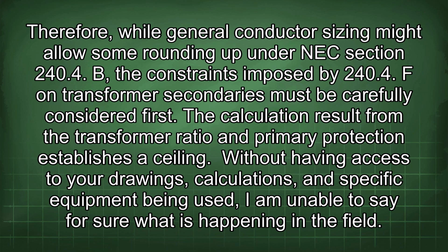Therefore, while general conductor sizing might allow some rounding up under NEC section 240.4(B), the constraints imposed by 240.4(F) on transformer secondaries must be carefully considered first. The calculation result from the transformer ratio and primary protection establishes a ceiling.